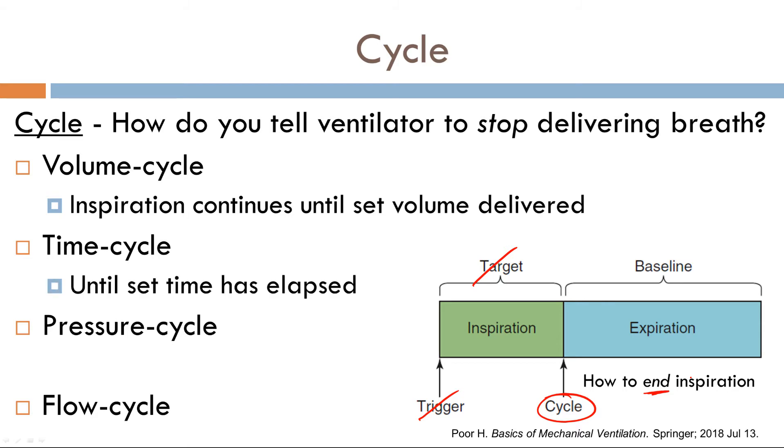What about time cycle? In time cycle, the vent will continue to deliver a breath until a certain time has elapsed. So for example, if I've set it to 1.2 seconds, once 1.2 seconds has elapsed, boom, stops delivering a breath.